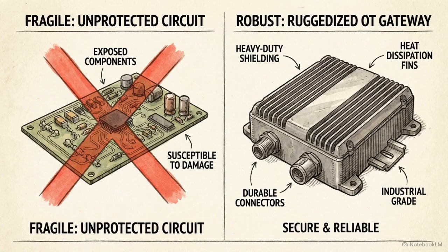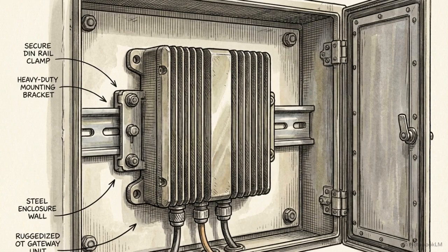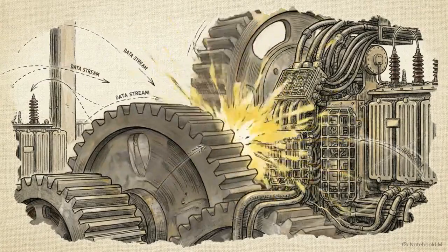This device acts as a local aggregator, filtering and processing signals before they leave the facility. A common engineering error is attempting to use consumer-grade IoT microcontrollers in an industrial setting. Those boards are exposed and fragile. Industrial monitoring requires operational technology-grade hardware, shielded in protective casings and mounted securely to DIN rails. The environment inside a high-voltage substation is hostile. Consumer hardware fails instantly under the massive electromagnetic interference and severe temperature fluctuations.